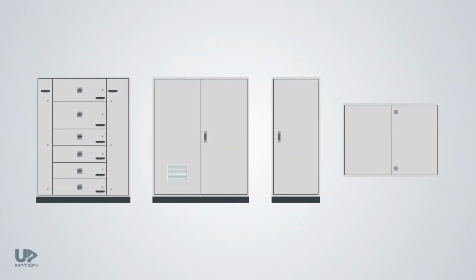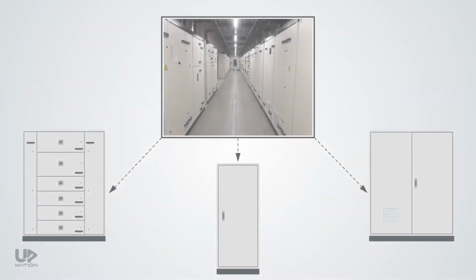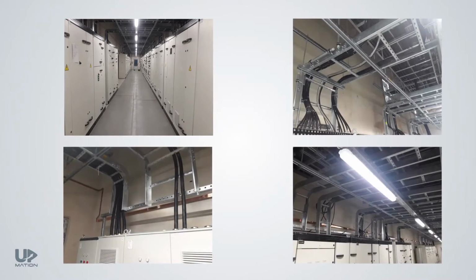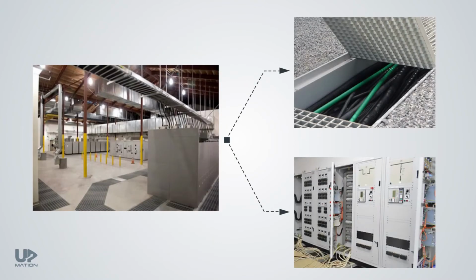Needless to say, there are additional reasons for reducing the size of panels. For instance, the larger the enclosure, the more metal is used on making that. The end result would be a higher cost. Inside of the control or electrical room, it is most likely that you only see floor-mounted cabinets. If you have ever noticed, in some electrical rooms, the cables are coming from the top side. In some others, the cables are laid on the bottom.